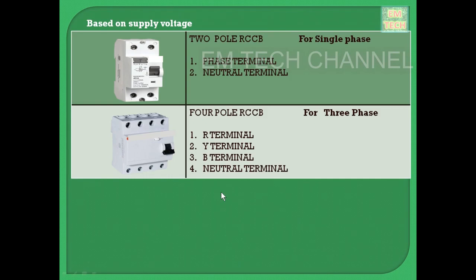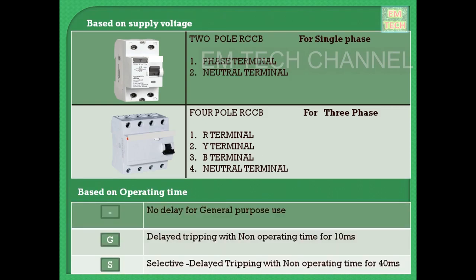Next, based on operating time. You can see in the first column of the table how the symbols will be printed on the RCCB. If it is left blank, there will not be any delay. Once the RCCB detects leakage current, it trips the circuit without delay. In the second row, you can see it printed as G. If the symbol is printed as G in a rectangular box, it means there will be a delay in tripping with a non-operating time of 10 milliseconds. Next comes S, meaning selective. If this symbol is printed on the RCCB, it means there will be a delay in tripping with a non-operating time of 40 milliseconds.